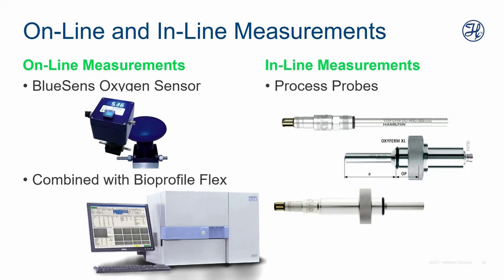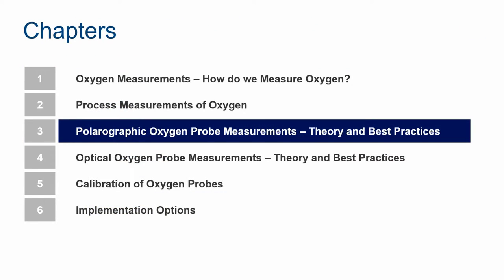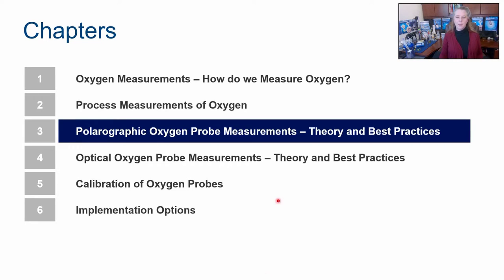So with that, process probes that can give you continuous measurements all the time, like a movie, are the best possible of all worlds, because they allow you to see what's going on always. They sit inside your bioreactor from the moment you start, and they feed you continuous data all the time. They give you a full picture. And when we're talking about oxygen measurements, that full picture is generally either done with a polarographic oxygen probe or an optical oxygen probe. The very first commercially available oxygen probes on the market were polarographic.